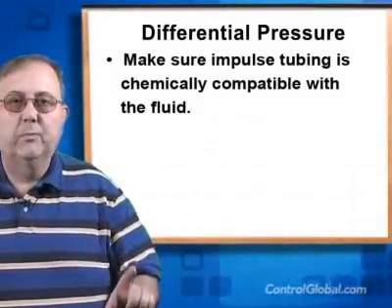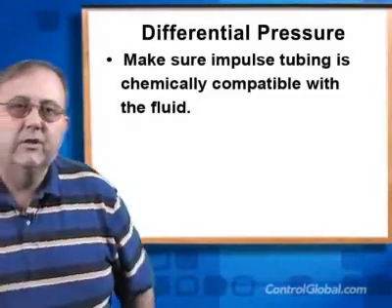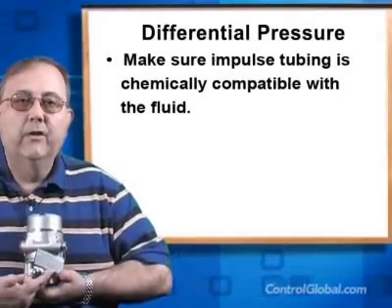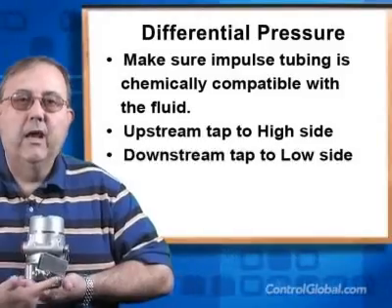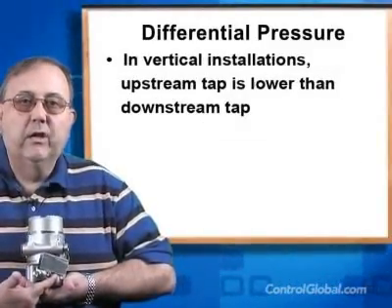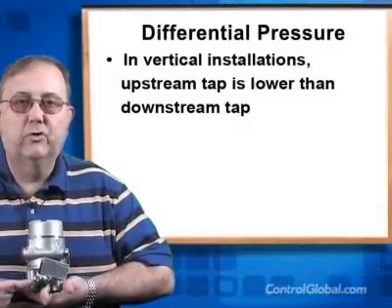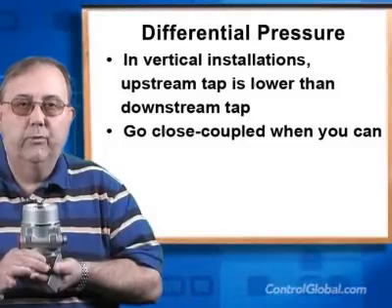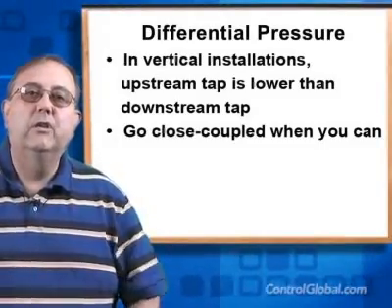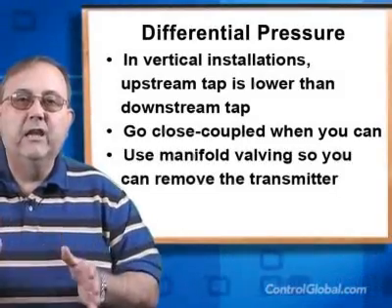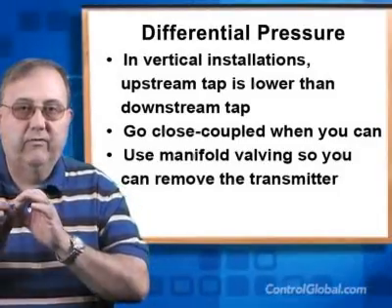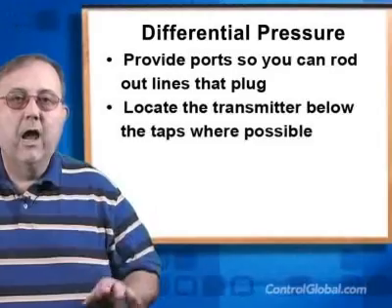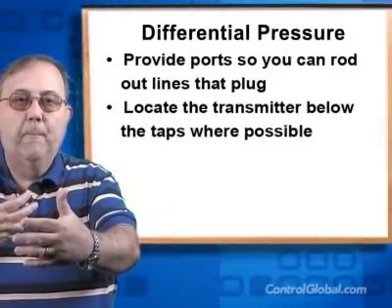The piping between the primary element and the transmitter is called impulse tubing. This is another source of potential problems and measurement error. Make sure the primary element taps are connected to the right ports on the transmitter — the upstream tap should be connected to the high pressure port and the downstream tap to the low pressure port. Remember that in a vertical installation, the upstream tap is below the downstream tap. If possible, use close coupled installations where the transmitter is close to or connected directly to the primary element. In hot applications, you can sometimes use the impulse tubing to cool the fluid. In freezing locations, you may have to heat trace the impulse lines. Impulse tubing should be kept full of liquid or gas, whichever you're measuring. Condensation should be avoided in gas applications, but in hot vapor applications, filling the impulse tubes with condensed vapor actually protects the transmitter.